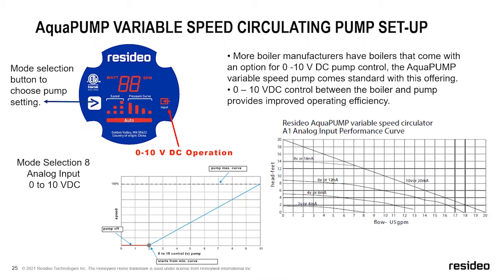Well, how often is that boiler on maximum firing rate? It should really only do that if it's calling for an indirect water heater or it's the coldest day of the year. Other than that, it should be modulating down. So the boiler will send a modulating output so that it can ramp the pump up or down around the boiler loop. So if it's at 50% firing rate, instead of needing 10 gallons a minute, theoretically, it would only need 5 gallons a minute. So I'm a big advocate, go with that.